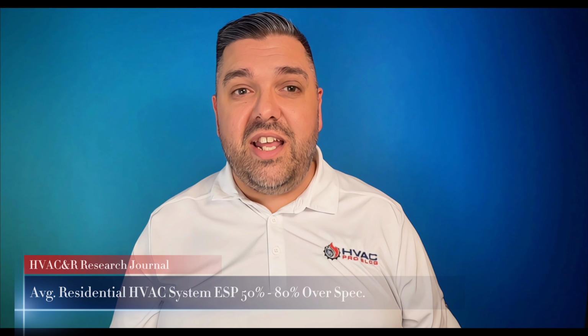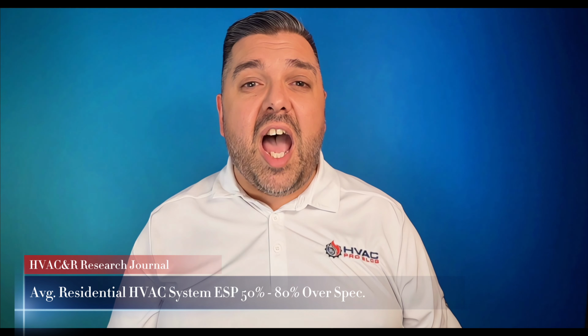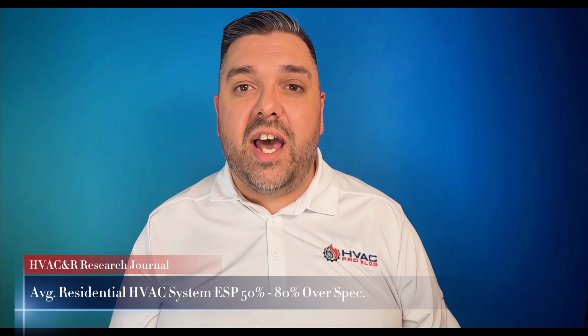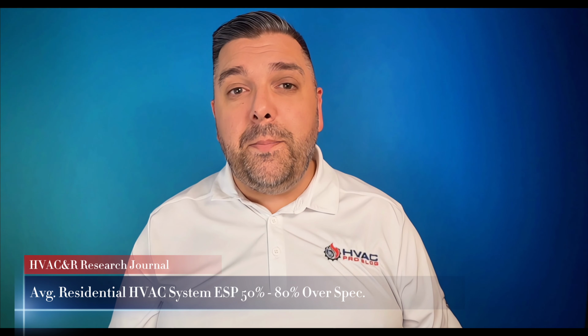Static pressure is another area where the industry has completely failed. According to a 2017 study in HVAC&R Research Journal, the average residential system operates at external static pressures 50 to 80% higher than equipment design specs. Every 0.1 inch of water column above design spec reduces airflow by approximately 3 to 5% according to manufacturer data. Here's what that means in plain English. Most systems are working way harder than they should to move less air than they need to. Equipment runs longer, uses more energy, fails sooner, and never delivers the comfort it's capable of.